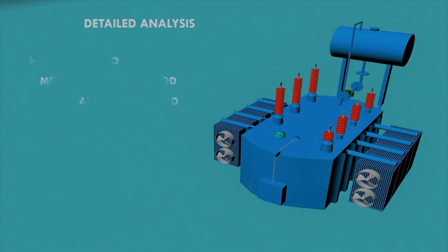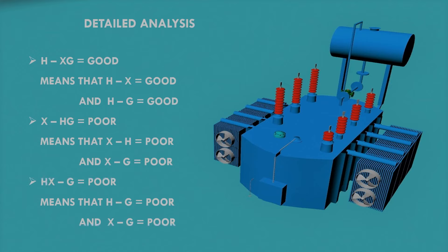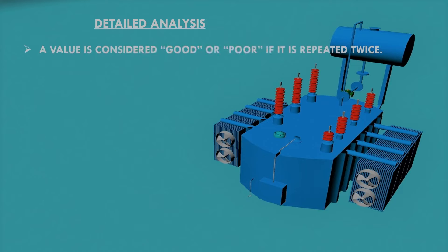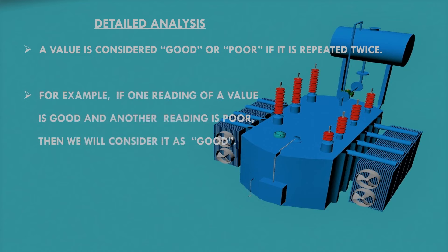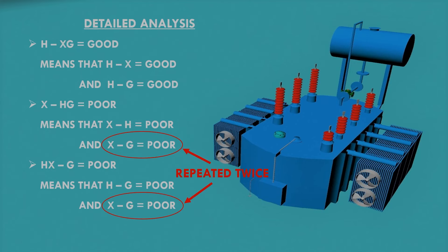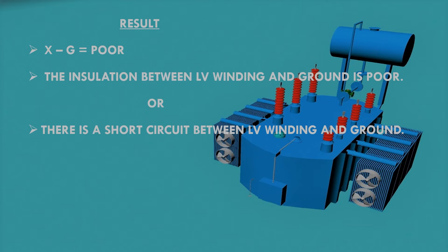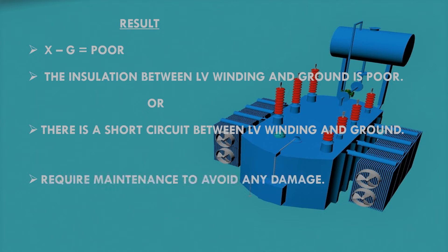The first corrected value is 150 mega ohm, which is satisfactory since the required value is 11 mega ohm. However, the second and third values are not satisfactory as they are lower than the required value of 11 mega ohm. From the second reading, HX is poor and XG is also poor. From the third reading, HG is poor and XG is also poor. A value is confirmed poor if it appears as poor in two readings. Here XG is poor twice, meaning the insulation between LV winding and ground is poor or there is a short circuit — requiring immediate maintenance.